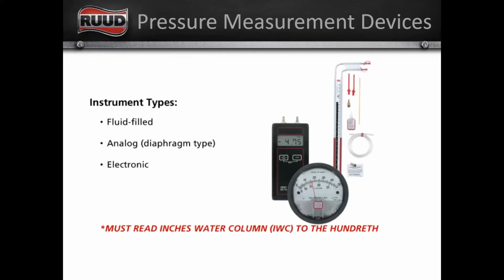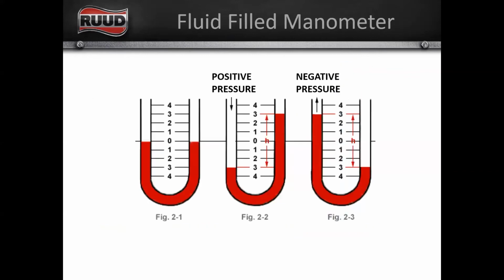The measuring device or the tool that we're going to use to measure our static pressure needs to measure inches water column in the hundredths, and we want it to go up to at least 2.5 inches water column. There's a couple different ways we can do that. We can do a fluid filled, which is real old school. That's the one on the upper right, which has some red fluid in it. It can be an analog, which is that dial, commonly referred to as a magnehelic gauge. Or we can have an electronic, either single or dual port manometer.